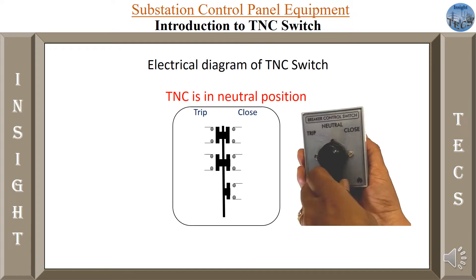As shown over here, this is a TNC switch — how it looks inside the panel, inside the control room. All these contacts are NO contacts, that is normally open. Whenever we move the handle towards either trip or close, these contacts will get closed. One important thing to understand is that in normal condition, the TNC switch is always in the neutral position.